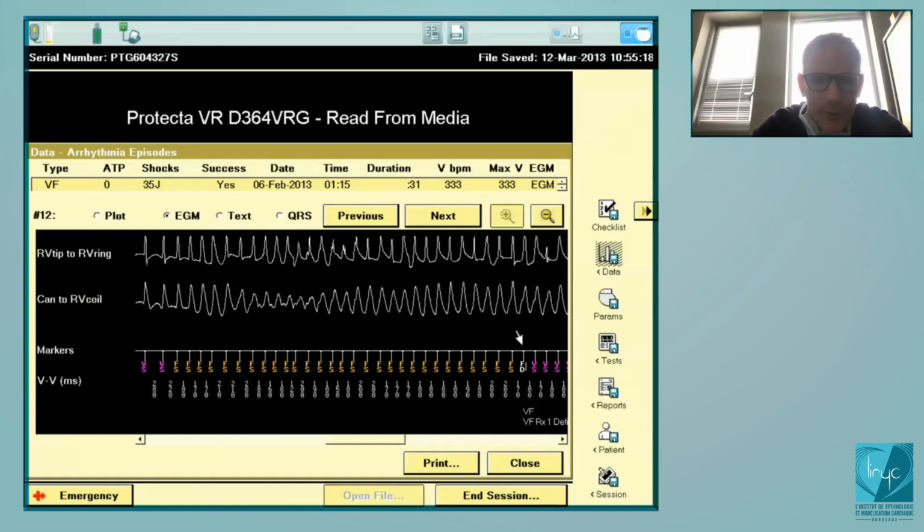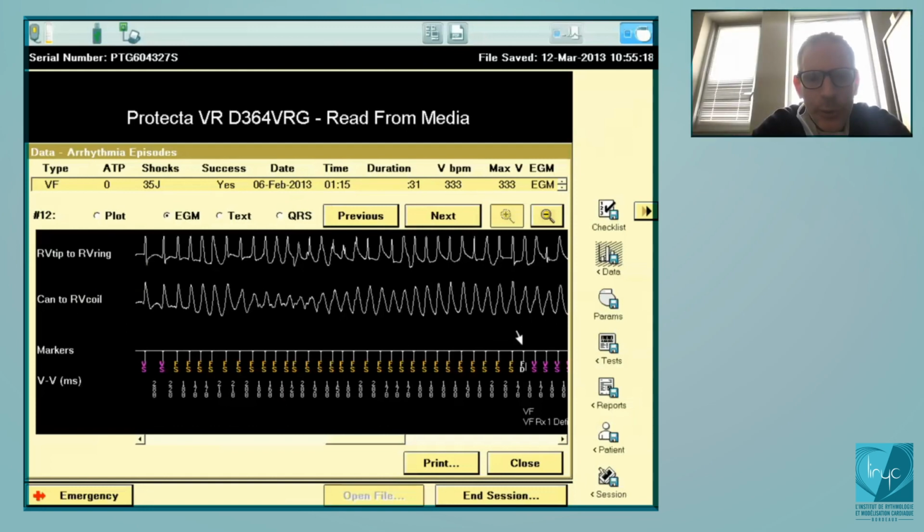If you have to summarize the VF counter, which word would you use? Probabilistic. Yes, probabilistic. It means that you require at least 75% of fast cycles. I will show you after how you can program it, but anytime the parameter will be 75%. You cannot change the percentage. You cannot ask for 80% or 60%. It's going to be 75%.